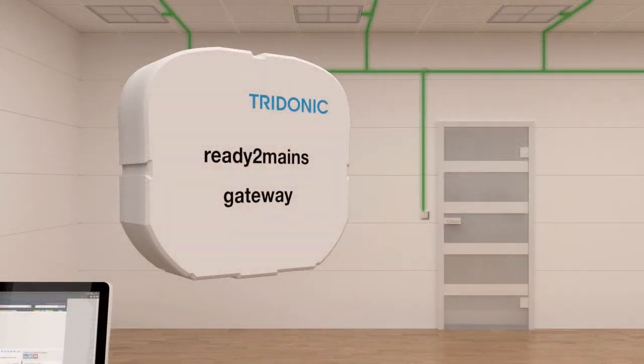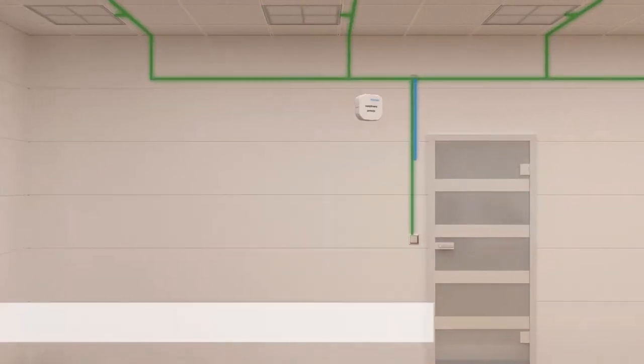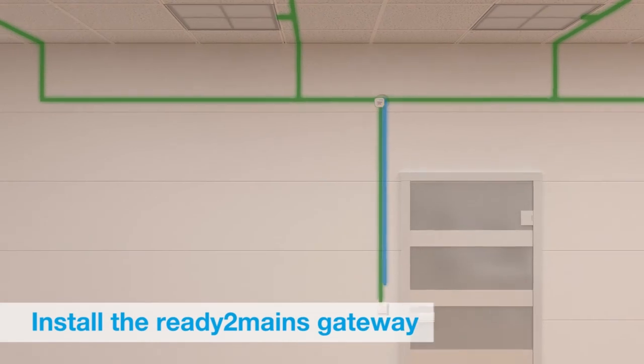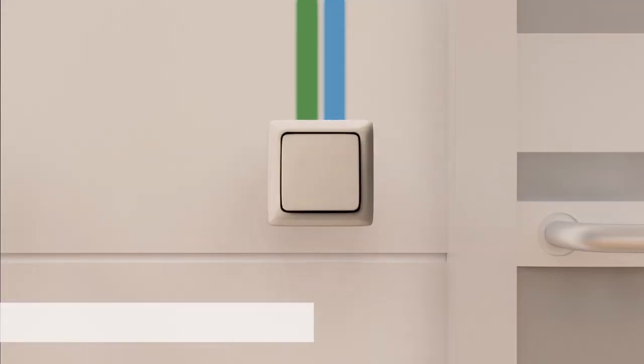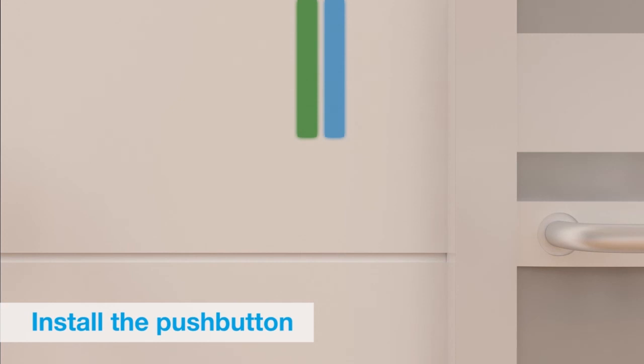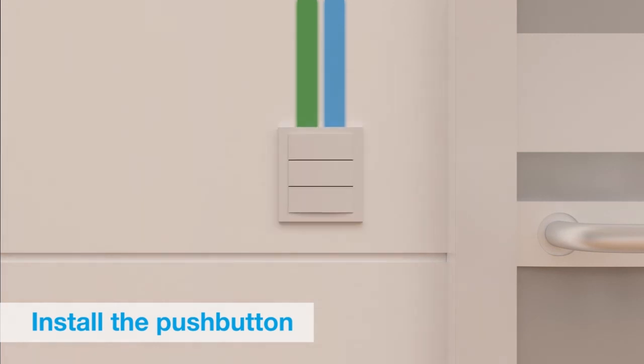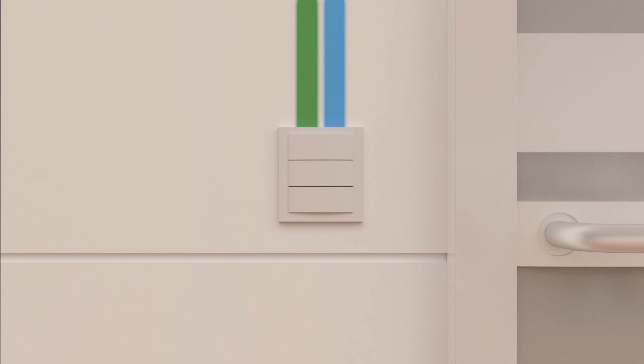The Ready to Mains gateway transfers the commands from the control unit onto the mains wiring. The simplest control is a push button but 1 to 10 volt dimmers or DALI lines can also be connected.